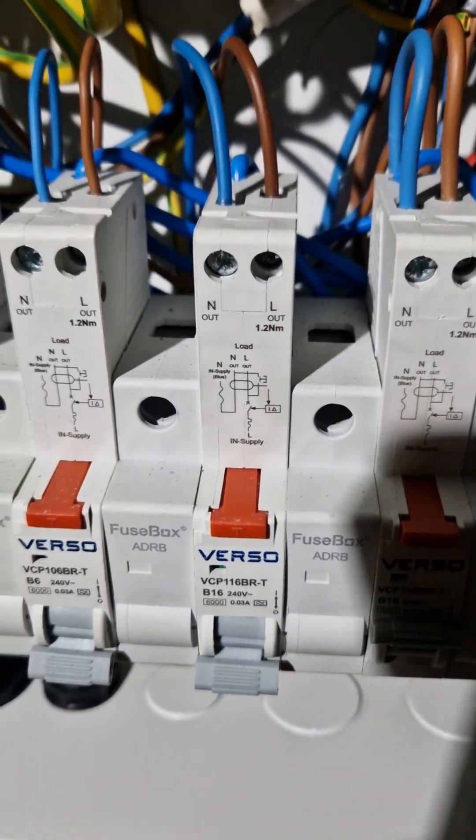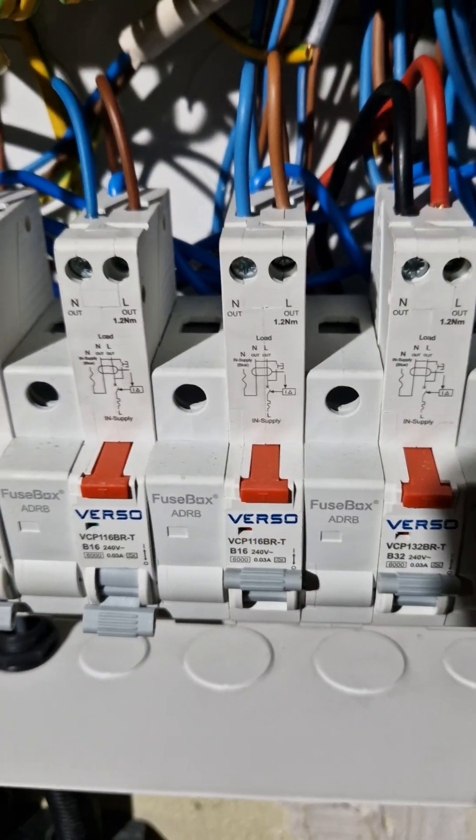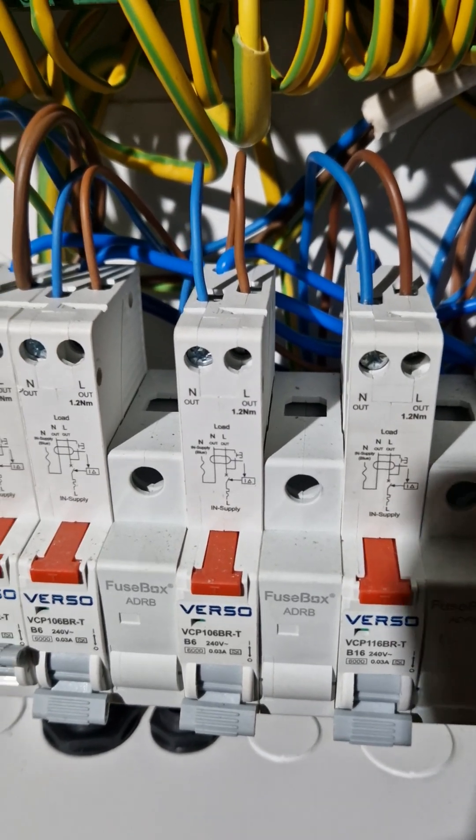The lights are tripping out. I've got a feeling they've got a shared circuit upstairs — maybe a shared neutral and a shared live. We'll have a look; I've got time to look at it now.